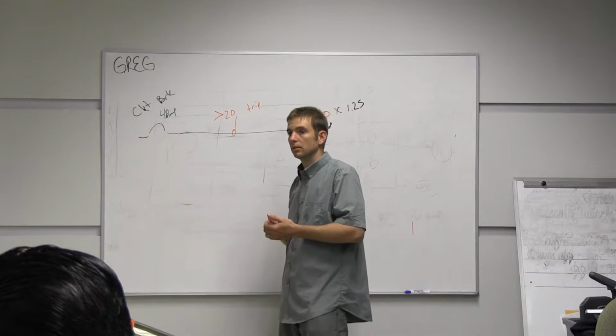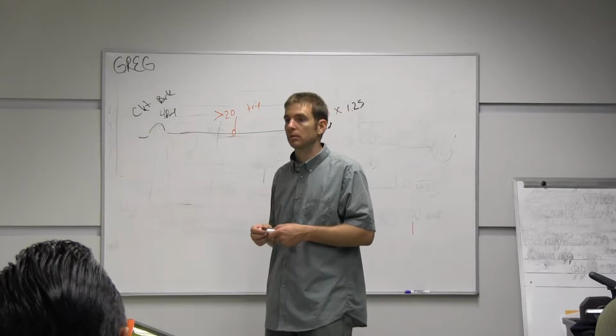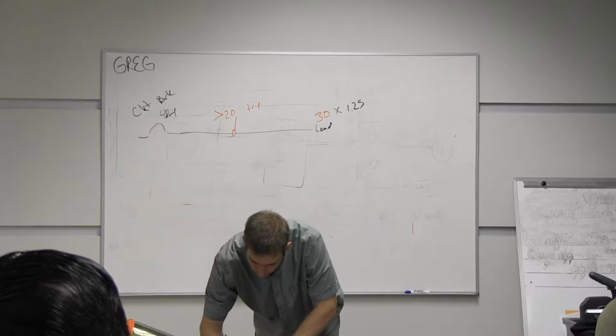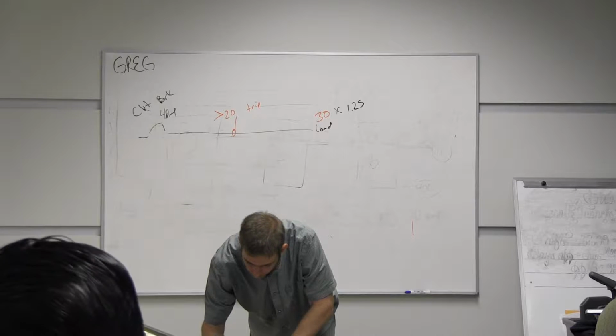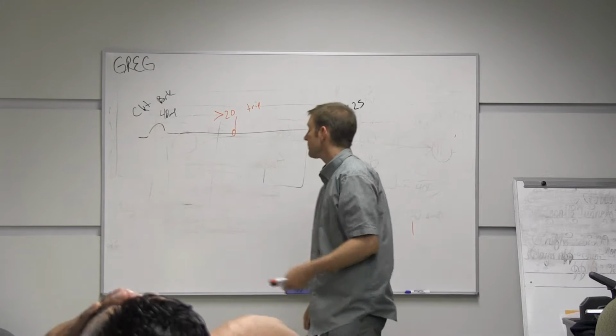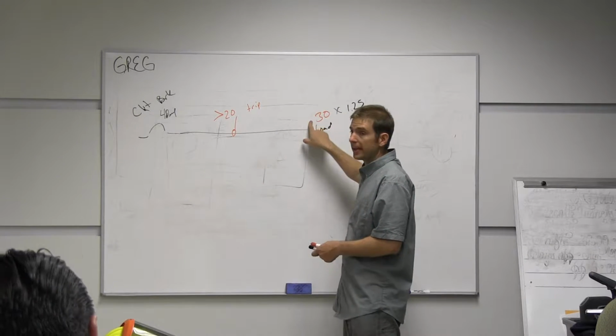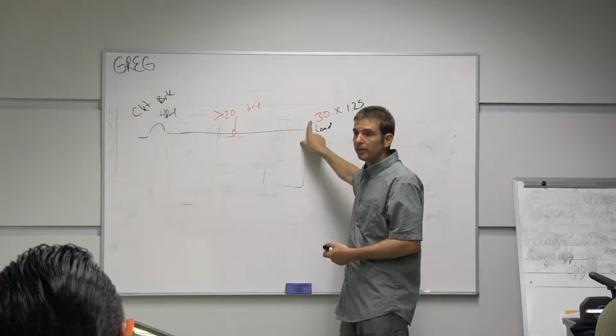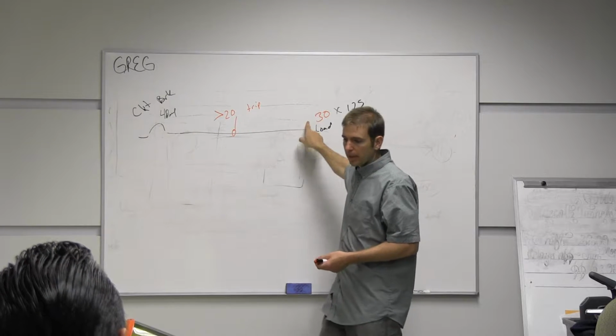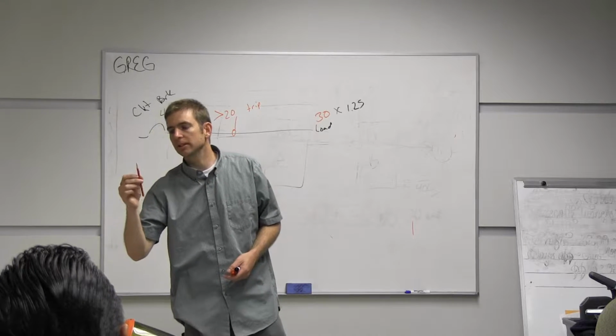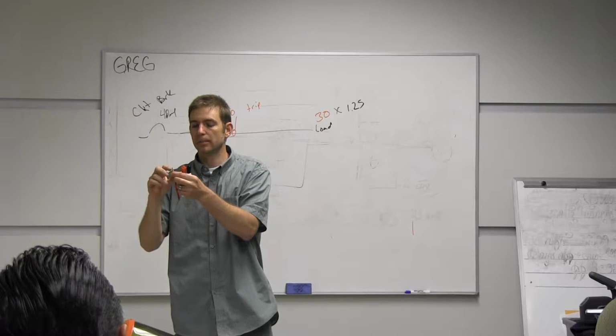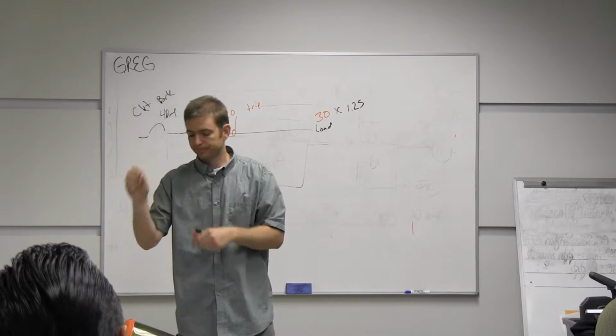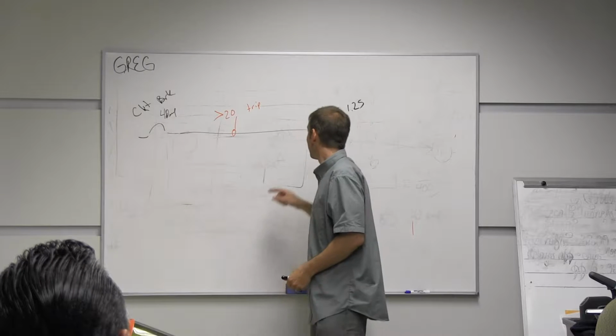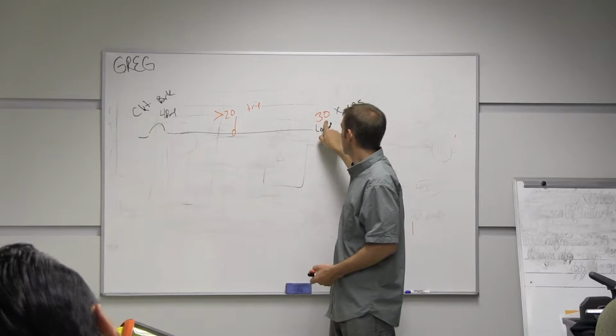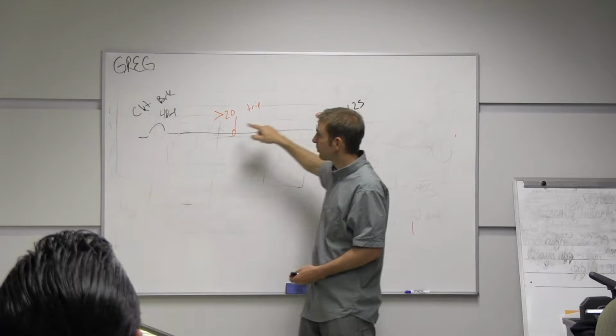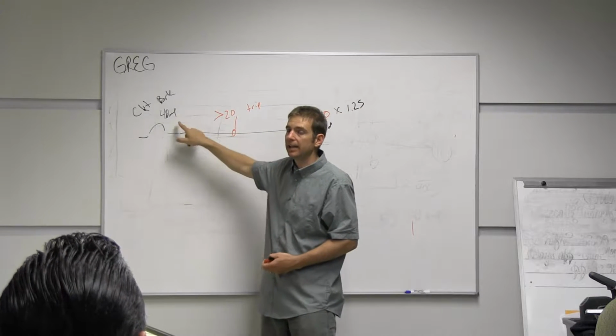Good question. Just a quick one. The breaker and the load, the wire has to match that circuit too, right? Or it could be a weak point. Yes, exactly. So I have 30 amp wire. I can get number 10 American wire gauge wire, which is about the size of a pencil lead on these colored pencils, the actual back, if you look at the back. So I can get a copper wire that size that will handle 30 amps, but because I'm running a continuous load and my overcurrent protection is 40 amps, I need to have 40 amp wire.